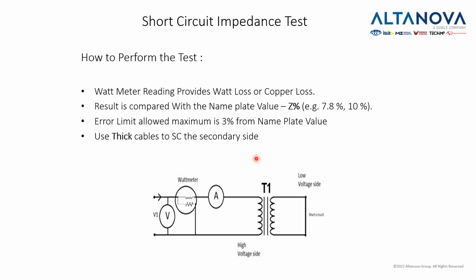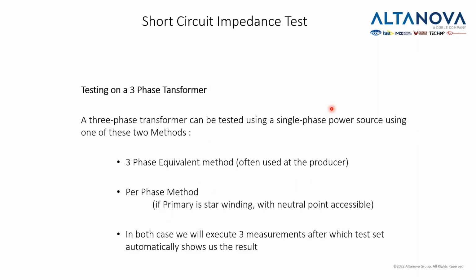And as we do that, we actually need to perform 3 different tests depending on which method we use, and we will see that in a second. And we need to compare that number with the number on the nameplate. That number can be, let's say, 7.8 or 10 or slightly higher or slightly lower. So if the result is 7.8, and let's say you have a transformer that is 100 on the primary to 10 on the secondary, that means if my Z percentage is 7.8, I actually need to generate not 100 on the primary to get 10 on the secondary, but 107.8, because 7.8 will be lost in the resistance of the copper. I hope that is clear.